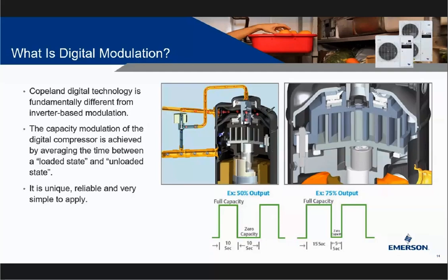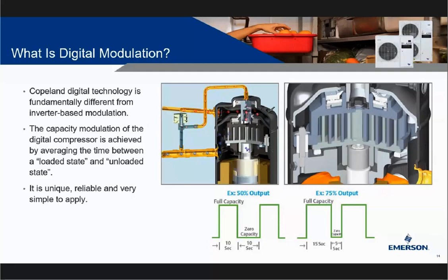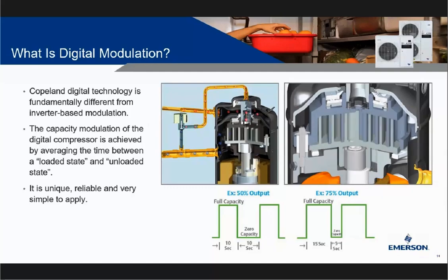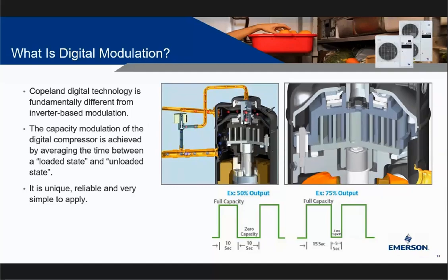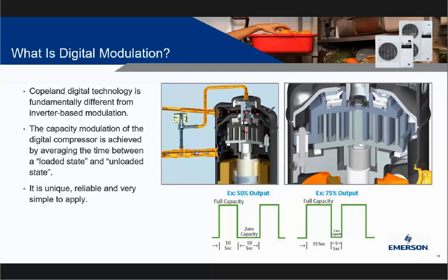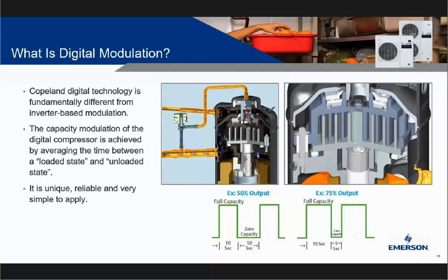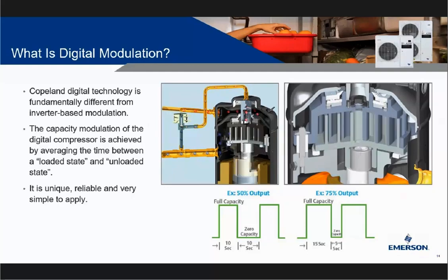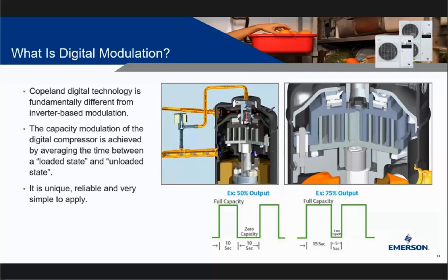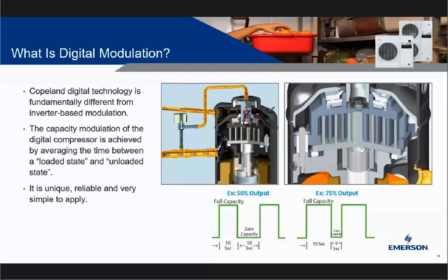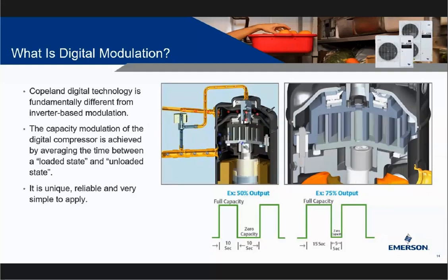So it's fundamentally different than an inverter-based technology. This is not variable speed, where the speed of the motor ramps up and down. Digital is actually simpler than that. Essentially, the controller that we discussed earlier, the XCM25D, will detect the demand coming back from all the various loads it's feeding. And I know I haven't shown this pictorially yet, but the digital does allow you to tie into multiple evaporators, so keep that in mind. So let's say this X-Line is tied to 4 evaporators. It's going to understand the demand from those 4 evaporators, and it will send signals to the solenoid valve on when to energize and de-energize.